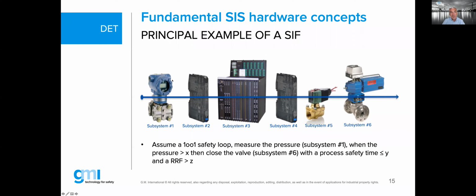You see here we are building the safety loop with different subsystems. We have a transmitter. We go through a barrier or GMI. We go into a safety PLC system. We go into a safety relay, called the interposing relay. We mainly will go into a solenoid, and the solenoid will take away the instrument air of your actuator, of a final element. Of course, it is not the correct picture, but just the principle. So assume that we have a one-out-of-one loop. That means we have a single sensor all the way to a single final element. That is the principle of the example we're going to use.